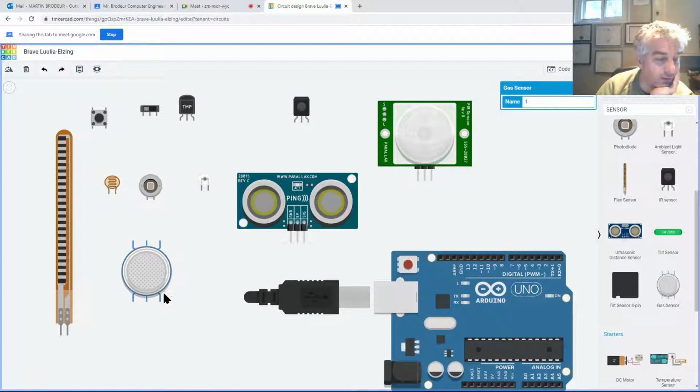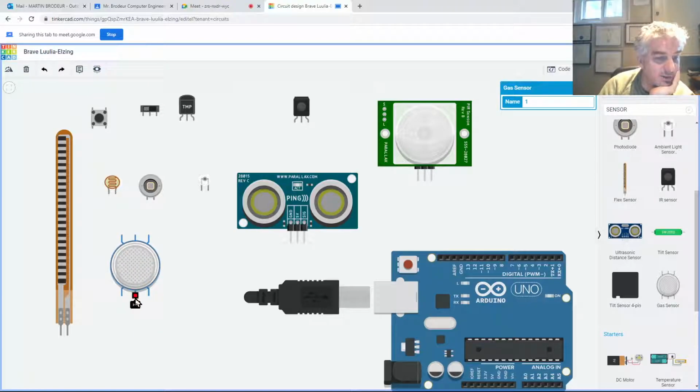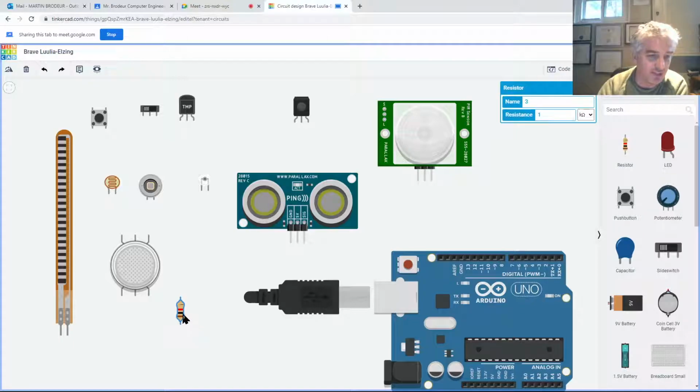Like these guys from the company, it was like $50 a pop. I'm like, I'm done. Once the second one stopped working well, I'm done with you. So I went online. These guys give off a resistance value when it's reading a safe, no gas presence, basically. And then I just bypassed it and put a resistor. I put something like this instead of this. So it's not sensing gas, but at least it's not giving me false alarms, because otherwise it's not working.